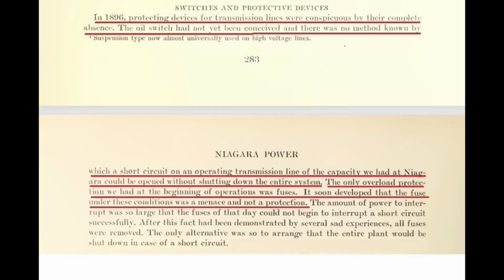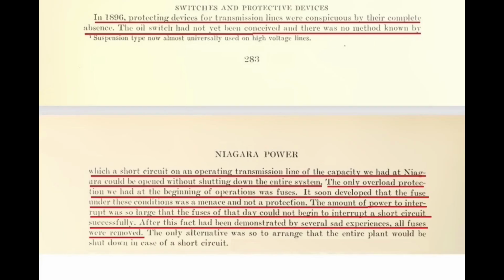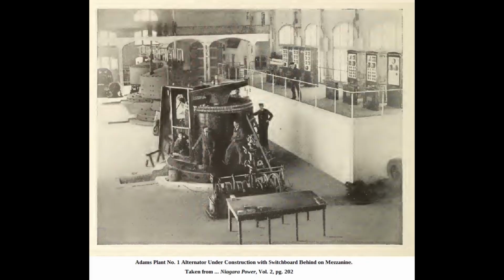The only overload protection we had at the beginning of operations was fuses. It soon developed that the fuse under these conditions was a menace and not a protection. The amount of power to interrupt was so large that the fuses of the day could not begin to interrupt a short circuit successfully. After this fact had been demonstrated by several sad experiences, all fuses were removed. The only alternative was to arrange that the entire plant would be shut down in case of a short circuit. This was accomplished by causing the field circuit breakers on the generators on the switchboard, shown here, to trip in case a short circuit came on and persisted.